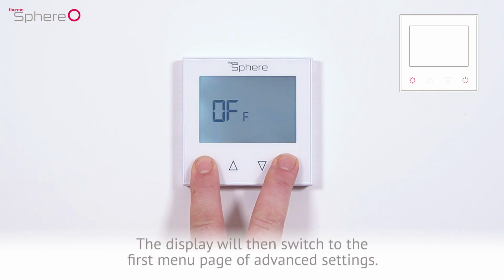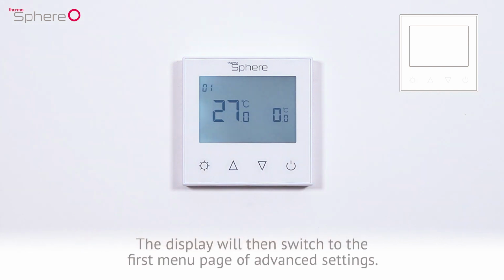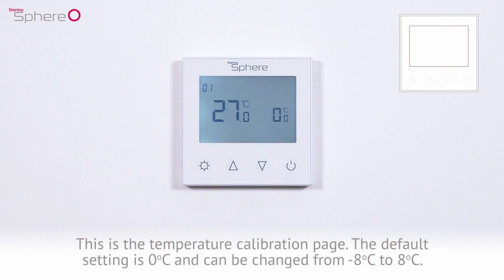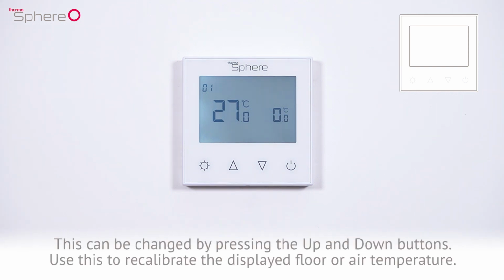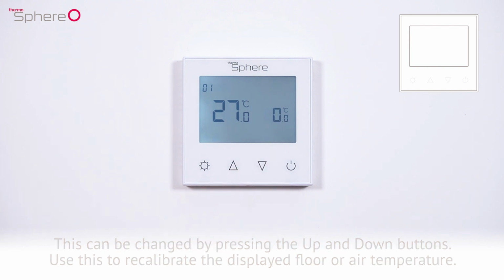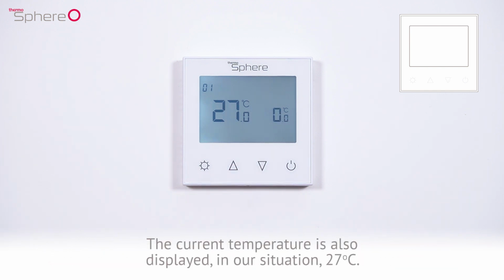The display will then switch to the first menu page of advanced settings. This is the temperature calibration page. The default setting is 0 degrees Celsius and can be changed from -8 degrees Celsius to 8 degrees Celsius. This can be changed by pressing the up and down buttons. Use this to recalibrate the displayed floor or air temperature.